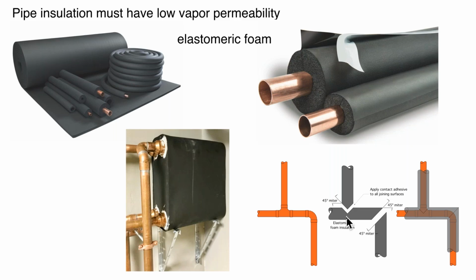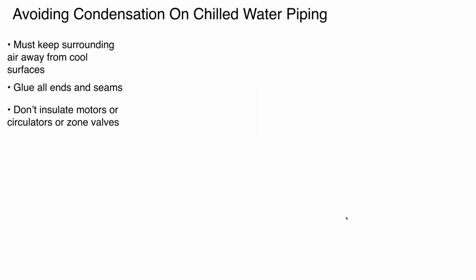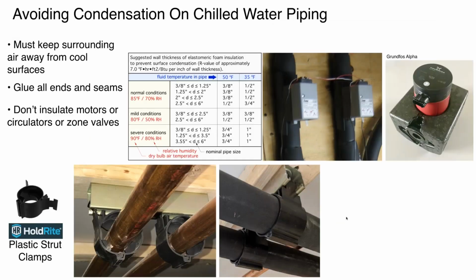So take the time to do it right. Make sure you insulate not only the piping, but as I say, the circulator volutes, as well as valves and air separators. Some components are available with insulation. I know Caleffi sells some components with insulation shells. Some manufacturers also have, over here on the right, here's a circulator from Grundfos that has an insulation shell available.